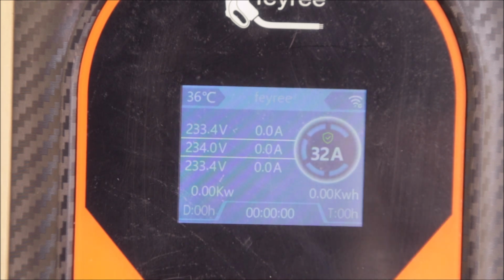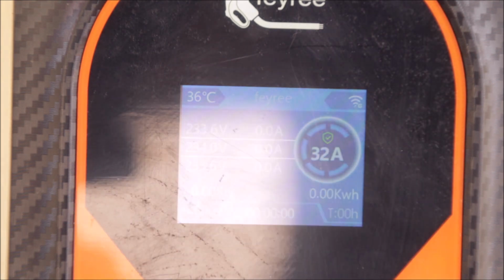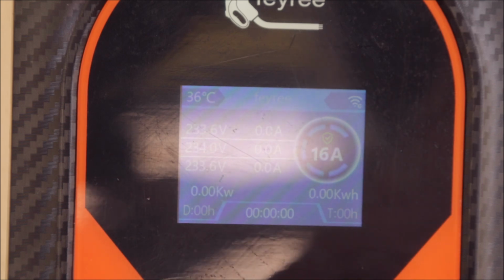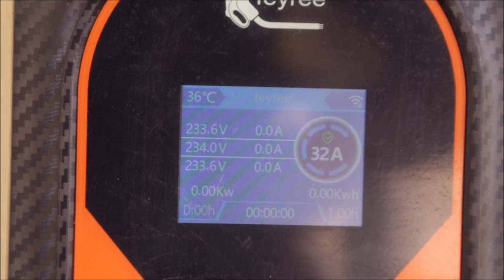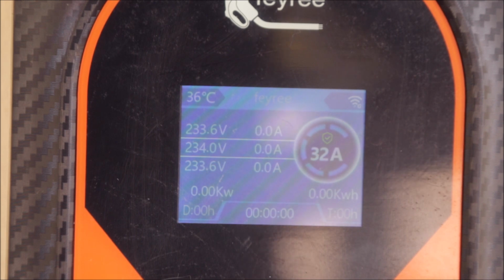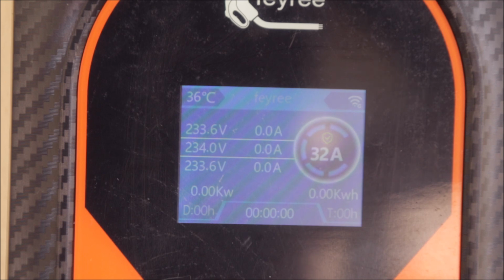Yeah, the wall box is showing us a nice display. We can see voltages, we can see the amperage which is set. The wall box is actually quite nice because you can set different output amps. So you can set, as you see, 8, 10, 13, 16, 25 and 32 amps. So if somebody does not want to charge as quickly and you want to maybe charge by the solar during the daytime, not use up too much energy at once, this can be also set here on the station.